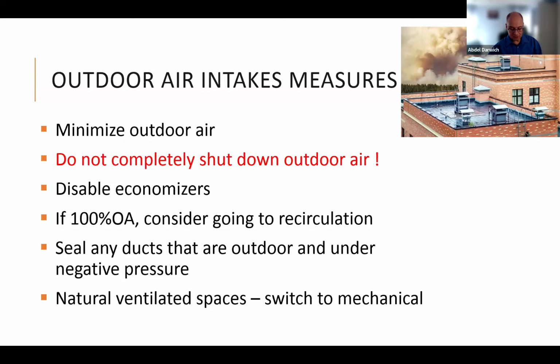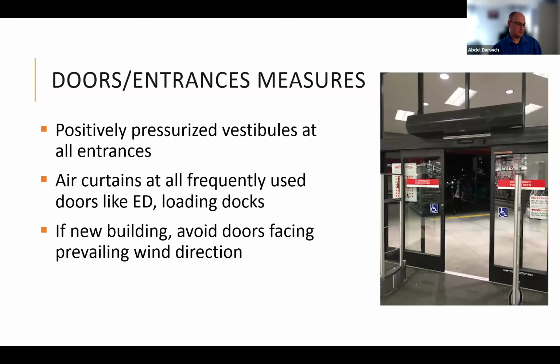Disable the economizer. We use economizers sometimes when the outside conditions are cool enough, so you use 100% outside air and you're not recirculating the air. Whenever there is wildfire smoke, it's not a good time to save energy, so we usually ask to disable economizers. You have to seal any ducts. If you have any ducts on the roof that are under negative pressure, that duct will suck wildfire smoke in. If you have a naturally ventilated space, well, that's not a good time to naturally ventilate it. So usually we ask people to switch to mechanical ventilation if there is a naturally ventilated space.